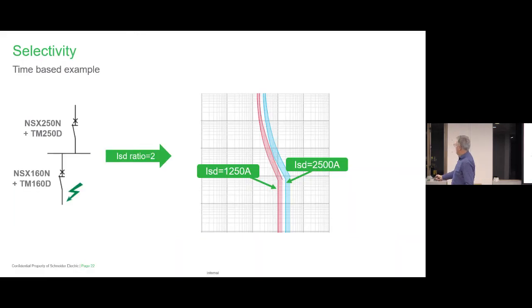But I think the previous slide mentioned that I can go back here. Yeah, because of the arc resistance, there's not enough energy to trip the upstream one. That's right. But that comes from basically the discrimination tables, which was based on empirical testing, I would imagine. Yes, you're ahead of me because that's in some of my other slides, but you're right. Between devices we can't show it graphically like this because it's very fast time. We're talking milliseconds that these things happen.